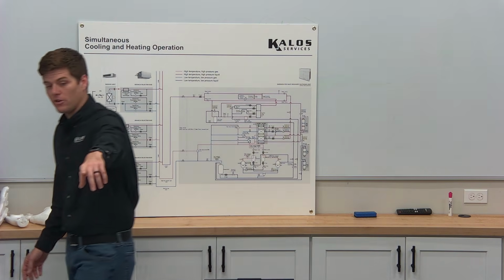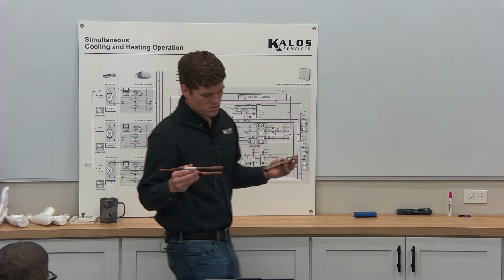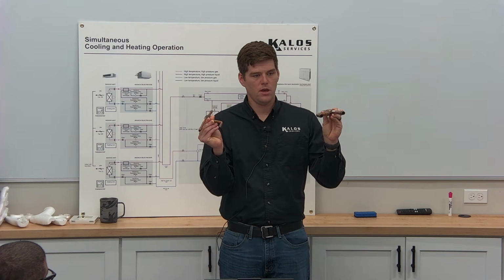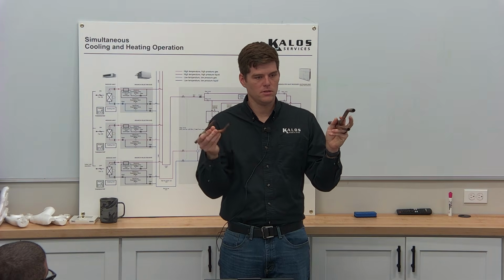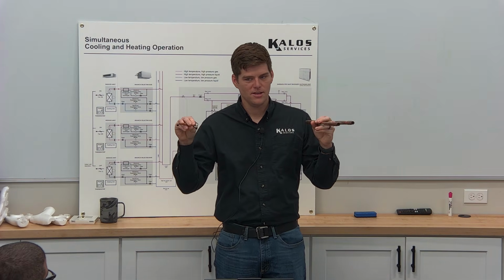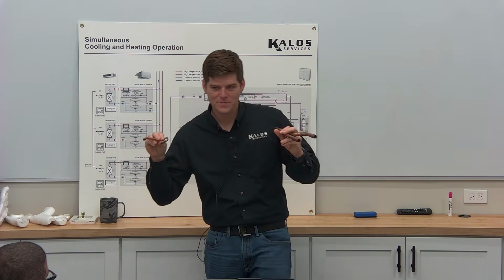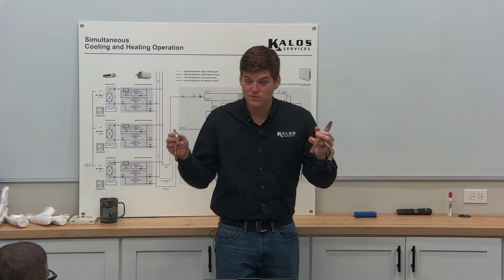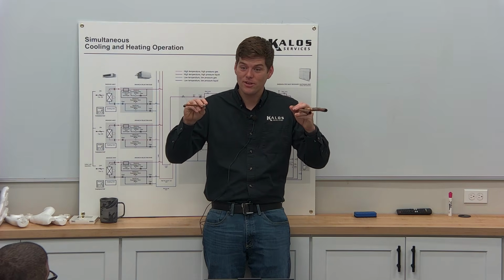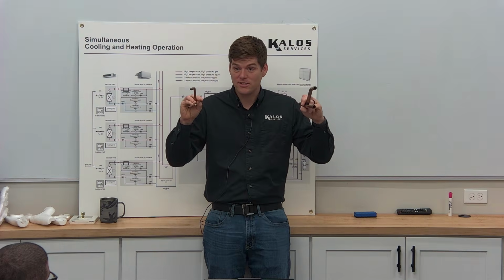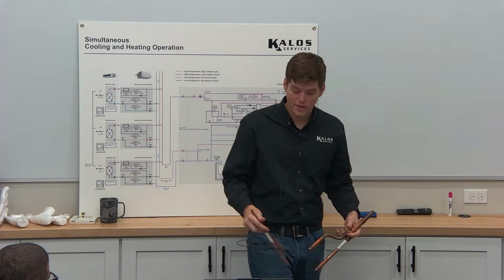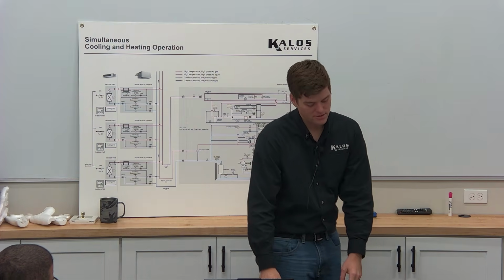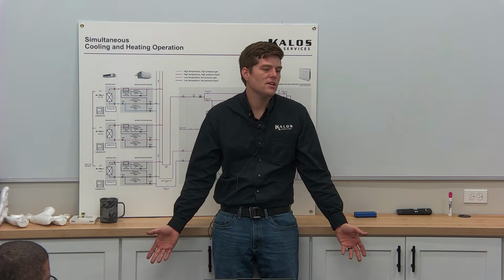So you'll notice how they're laid out on the table right now. Let me ask you this question. Does anybody know which way these should be installed? This way, this way, this way. What do you think is going to be the most? I'd probably say horizontal. Yeah, that way. Why is that? Just to keep the path. Path of least resistance, right? To keep it equal. You change this, right? Gravity's different. I mean, it may be a small amount up, right? But when we install these, when we see these in the field, they're supposed to be plus or minus 15 degrees off of level. Slight deviation isn't going to kill it.